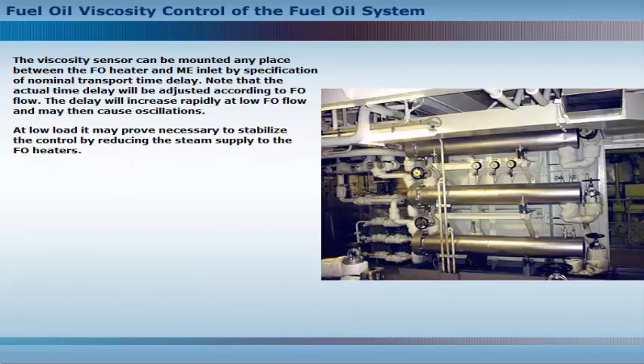Note that the actual time delay will be adjusted according to fuel oil flow. The delay will increase rapidly at low fuel oil flow and may then cause oscillations. At low load, it may prove necessary to stabilize the control by reducing the steam supply to the fuel oil heaters.